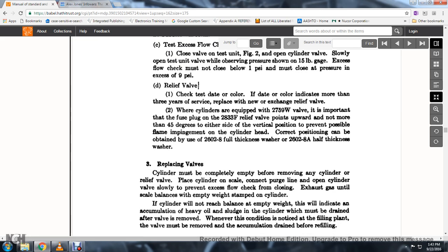Check the test date and color; if the date indicates more than three years of service, replace with a new or exchange relief valve. When the cylinders are equipped with the 2759W valve, it is important that the fuse plug 2833F relief valve is positioned upward not more than 45 degrees either side of the vertical position to prevent possible flame impingement on the cylinder head; the correct position can be obtained by using the 2602-8 full thickness washer or 2602-8A half thickness washer.